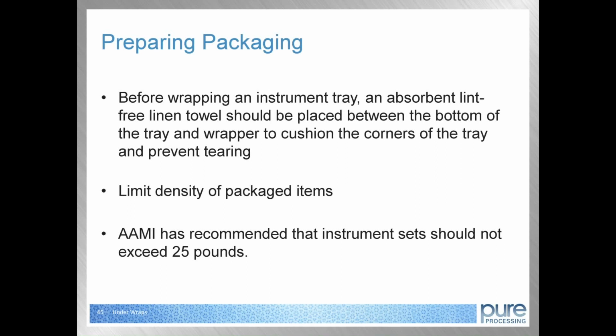Before wrapping an instrument tray, an absorbent lint-free linen towel should be placed between the bottom of the tray and wrapper to cushion the corners of the tray and prevent tearing, as well as to serve to absorb the condensation during steam sterilization. Density is a key factor related to the sterilization of items. The more densely items are packed, the greater the percentage that the sterilant will not contact the surface areas of all items, and drying will be inadequate. ANSI AAMI recommends that instrument sets should not exceed 25 pounds.